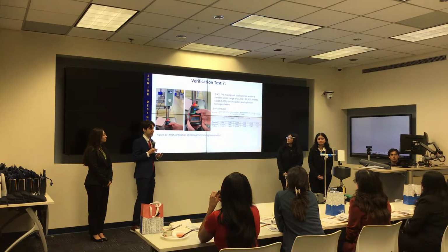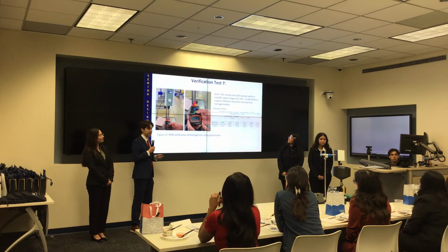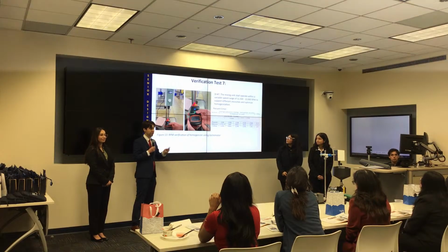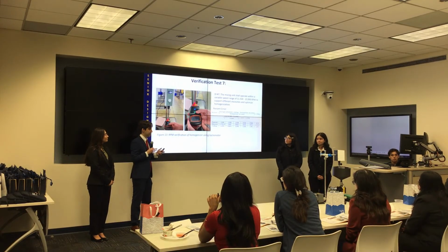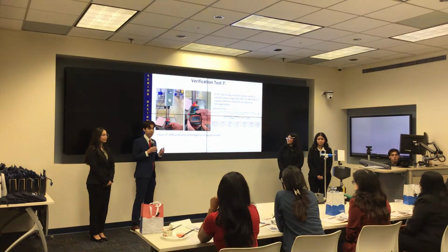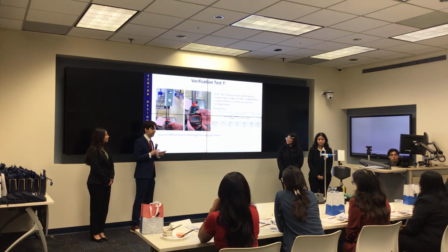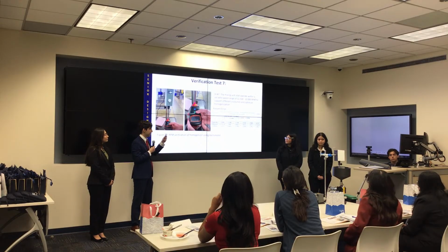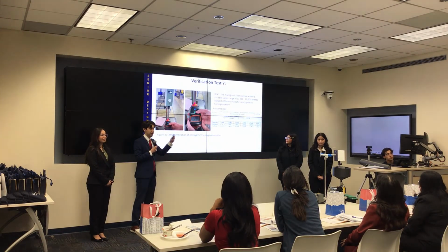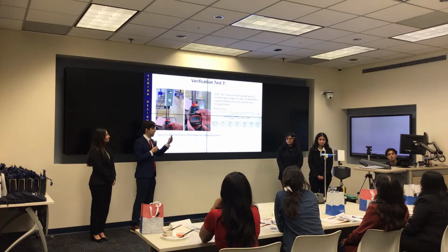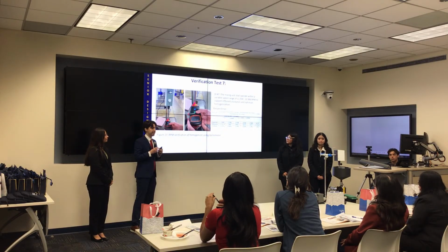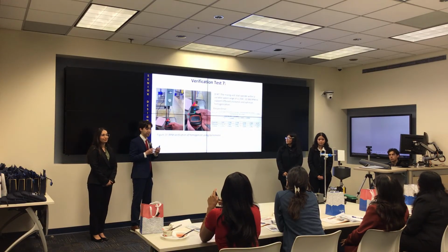Some of the most important ones include the RPM measurement test, in which we used a laser tachometer to ensure that the homogenizer that we purchased met the metrics that we set forth in order to break up larger particulate without damaging bacterial viability. And we ran a series of tests across the entire range of our RPM values, and we found a percent error of only 1%, meaning that this was a reliable device that we could use in our system.